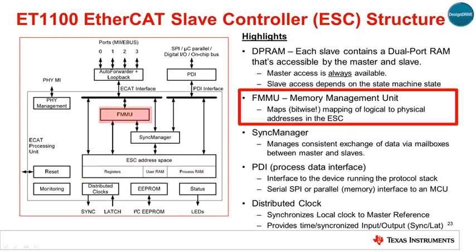The FMMU, or Fieldbus Memory Management Unit, is responsible for converting logical addresses for slave data into physical addresses via an internal table. Addressability is down to the bit level. It's this flexibility that enables a single EtherCAT command to address multiple slaves and achieve very high utilization of available system bandwidth.